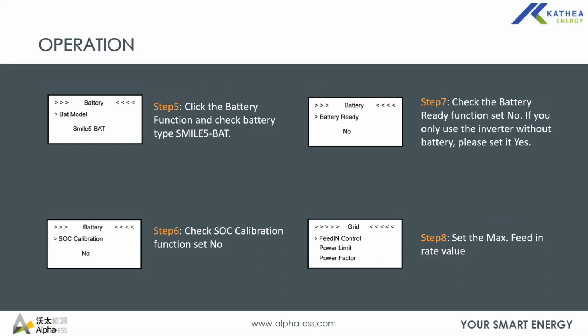On battery, everything comes default. The system will automatically pick up the type of battery connected to it and the number of batteries connected, in terms of capacity. So if you have 1 battery, the capacity will be 5.7 kilowatt, and if you have 2 batteries, 11.4. So on the battery setup, you just need to scroll and confirm that the right capacity has been detected. If not, then you need to check if your DIP switch number 2 on the left battery is on, such that it picks all the batteries above that battery.